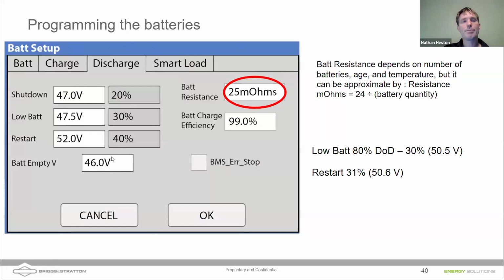This is to protect the battery, so it will turn the inverter completely off, not just the loads off, when we reach this voltage, to protect the battery so that battery BMS doesn't shut itself down. Battery resistance, this actually varies a lot with temperature. It can be approximated by 24 milliohms divided by the number of batteries you have. However, if you're in extremely cold environments, you might want to increase this number.